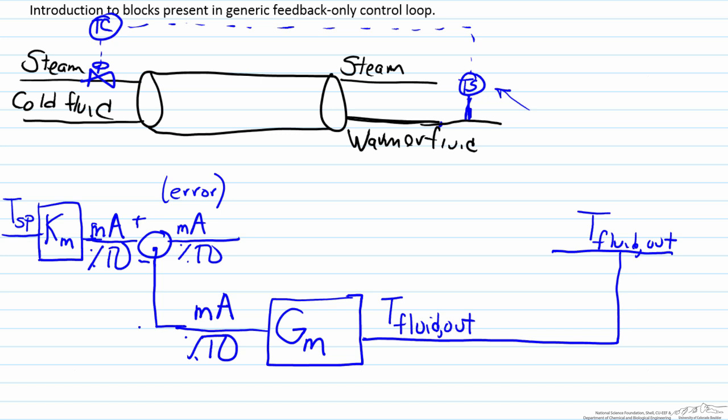If we follow our diagram here, the value of the sensor through this dashed line gets sent to our controller, which is represented as GC. GC will take in that error in percent transmitter output, and will output a signal usually in percent controller output, basically saying this is how active the controller should be.